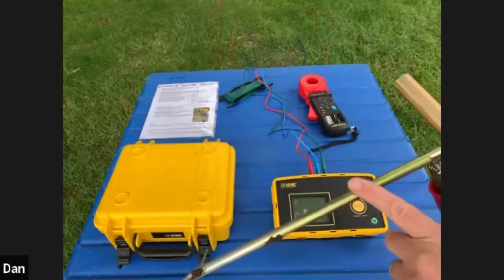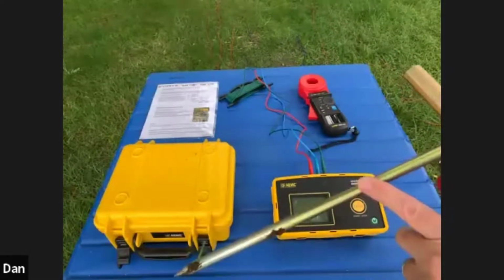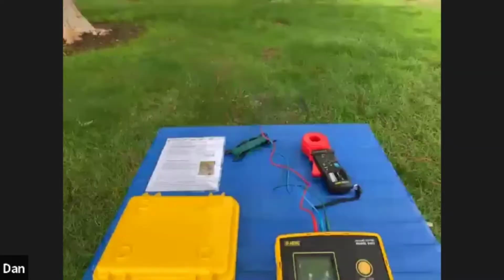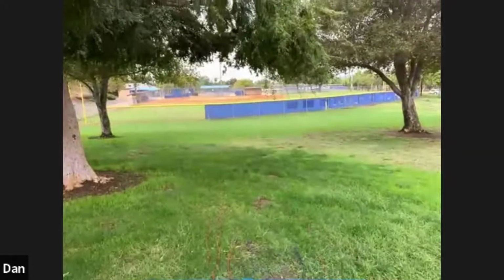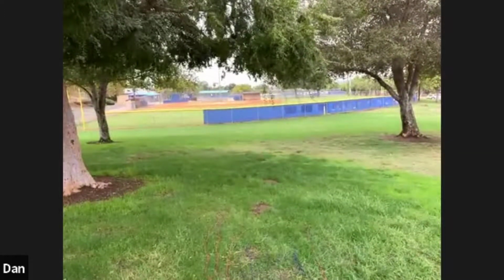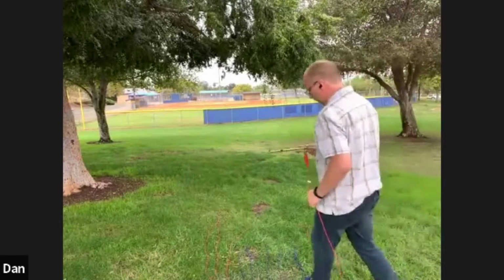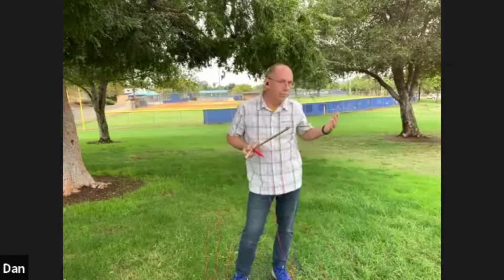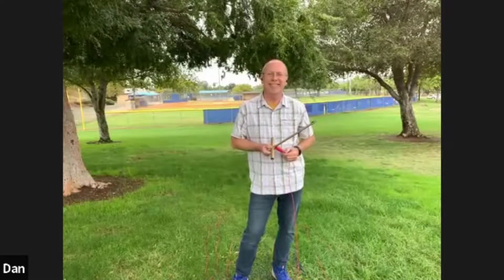Now we're going to go out 10 times the length of my grounding rod. Idral, ready with your calculator? If I've got an 8-foot rod, I want to go out 10 times the length of that. What's the math? That's an easy one, 80. Good, 80 feet. So we're going to go out 80 feet.